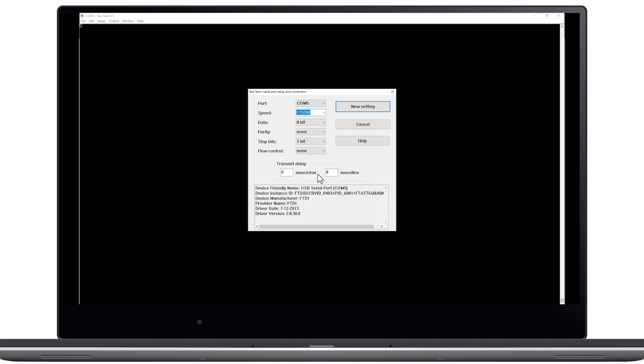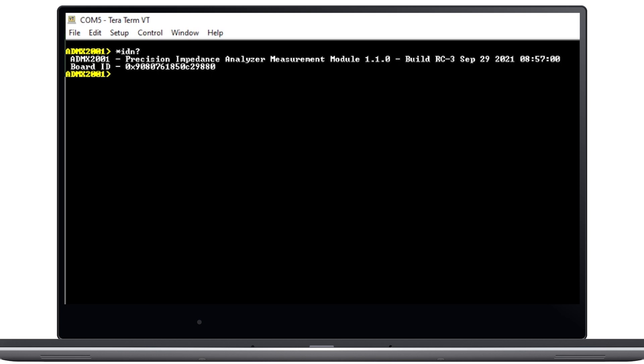Press ENTER within the terminal and the ADMX2001 prompt should appear, indicating that you have established communication to the module. If you want to verify further, type the command *IDN? and press ENTER and you will see the firmware version and your module's unique ID.